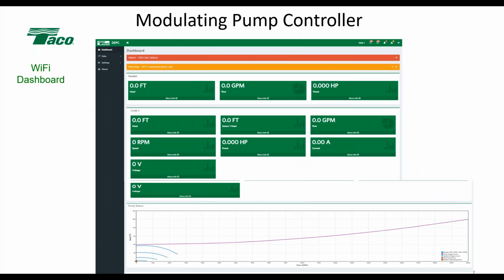Okay. So I told you there was a Wi-Fi dashboard. If I connect to that pump via Wi-Fi, I get a screen like this. And it gives me all the parallel information. So across the parallel information, it tells me the head, the flow, and the horsepower in parallel for all the pumps that are operating. And then below that is an individual pump screen. So if I'm connected to chilled water pump number 1, it's going to give me the flow, the head, the power, everything that it's seeing at that point in time for that individual pump. And then down below, of course, is your pump and system curve. And normally there'll be dots on there where the pump is actually operating.